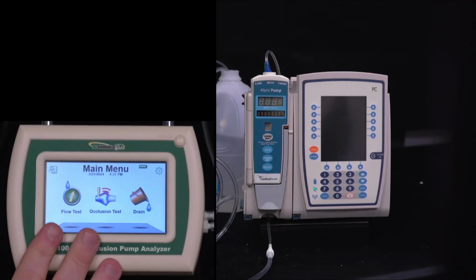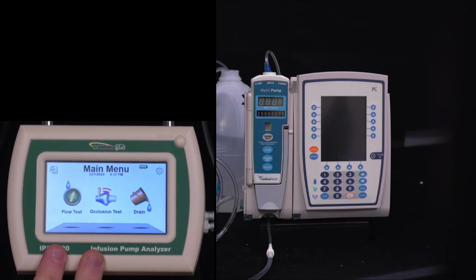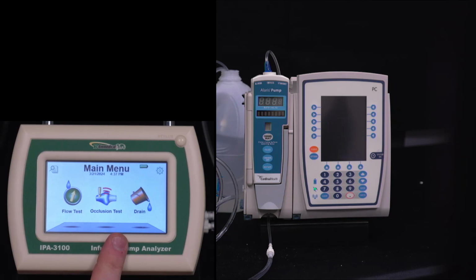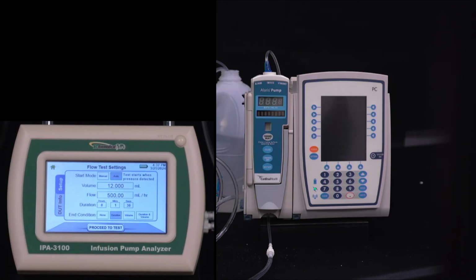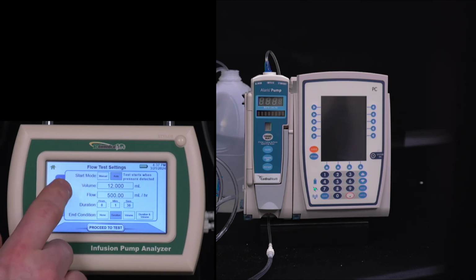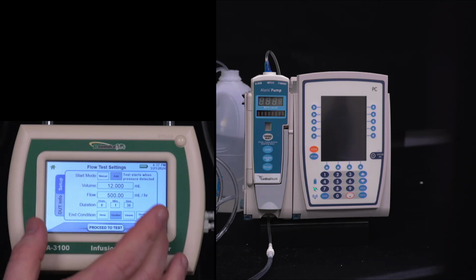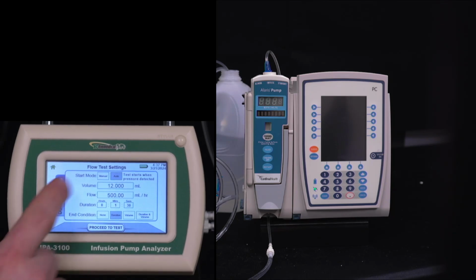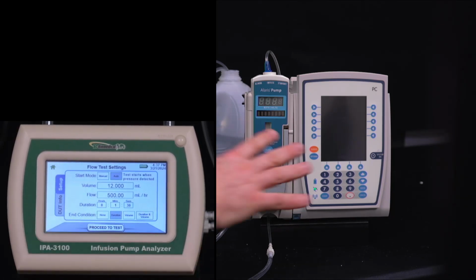Now, the first thing I want to show you is just running manual tests with the unit. So we would either do a flow test or an occlusion test. So let's start with the flow test. Now I need to configure the IPA 3100. It has a setting for the flow rate and the volume delivered, just like on the pump.